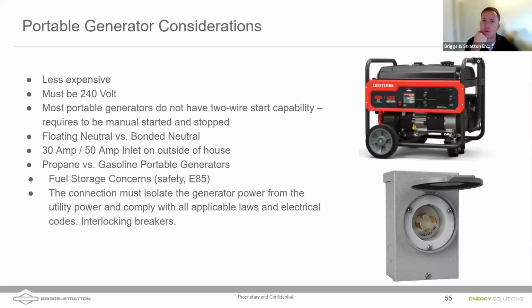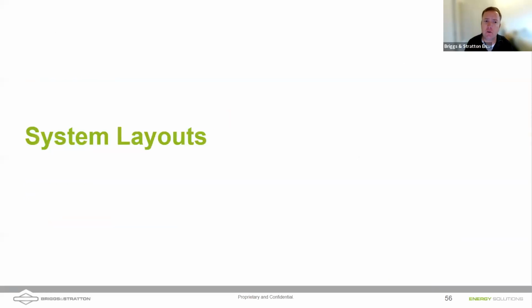One thing I don't want to get too deep into, but my concern is that a lot of these portable generators have the frame of the generator and the alternator bonded together. If we think about the National Electric Code, we only want one location in our house where the neutrals and the ground are bonded together, and we don't want to induce some concerns or risks. So all of these portable generators are a little different — open up the manual, read what it says, and understand whether or not you have to unbond the frame of the generator to the alternator. I'm not going to get into specifics because each generator can be a little unique.